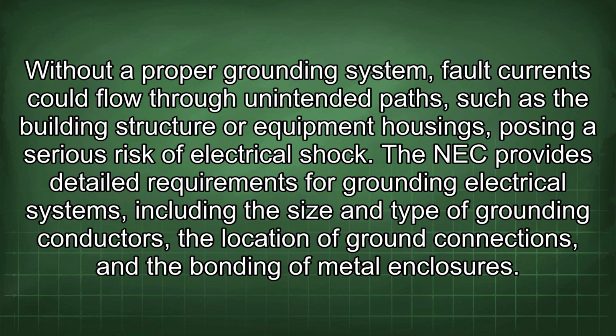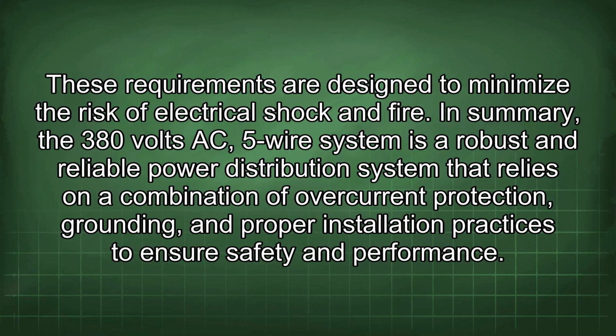Without a proper grounding system, fault currents could flow through unintended paths such as the building structure or equipment housings, posing a serious risk of electrical shock. The NEC provides detailed requirements for grounding electrical systems, including the size and type of grounding conductors, the location of ground connections, and the bonding of metal enclosures. These requirements are designed to minimize the risk of electrical shock and fire.